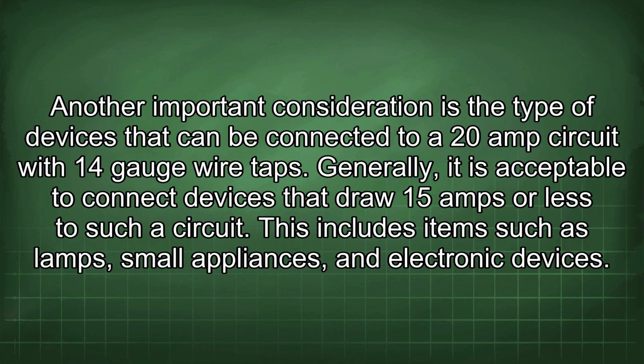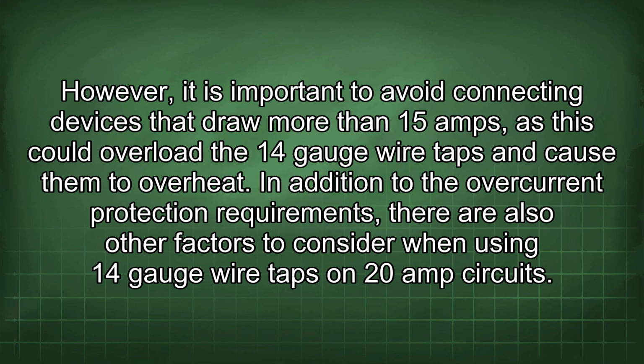Another important consideration is the type of devices that can be connected to a 20-amp circuit with 14-gauge wire taps. Generally, it is acceptable to connect devices that draw 15 amps or less to such a circuit. This includes items such as lamps, small appliances, and electronic devices. However, it is important to avoid connecting devices that draw more than 15 amps, as this could overload the 14-gauge wire taps and cause them to overheat.